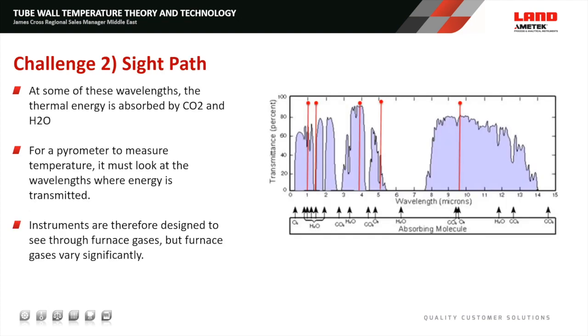The second challenge is the sight path. At some wavelengths, thermal energy emitted from tube walls is absorbed by CO2 and H2O. We need to ensure our pyrometer is operating in what we call an absorption window. If we do that, none of the energy emitted from the tube wall is absorbed by H2O or CO2, giving us good transmittance and no errors caused by the atmosphere between the tube wall and the pyrometer.